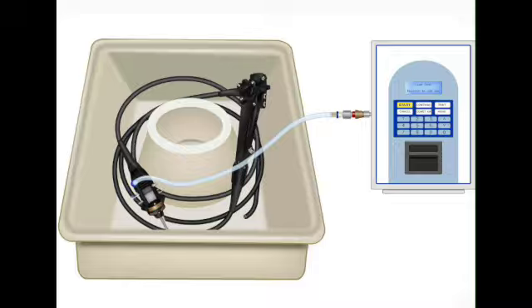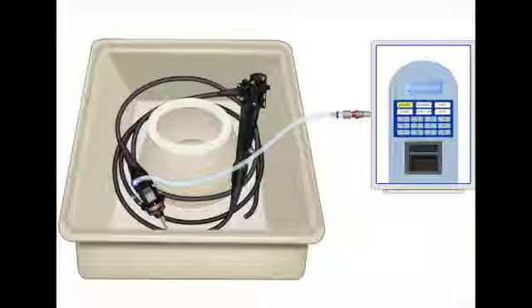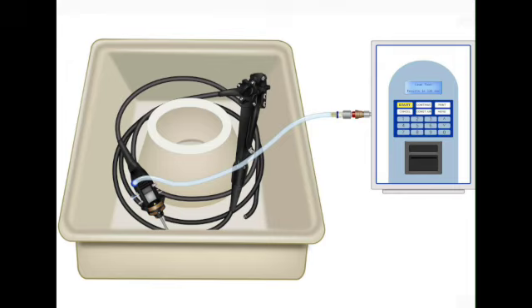There is a very specific step. You have to infuse exactly 60 cc's of water through the suction port while it's underwater. 60 cc's, that's so precise. Why? It's designed to put just enough stress on the seals around that suction channel. That channel is a major pathway for contamination, so you have to be absolutely sure it's secure. You push the water through and watch for any bubbles at the distal tip.